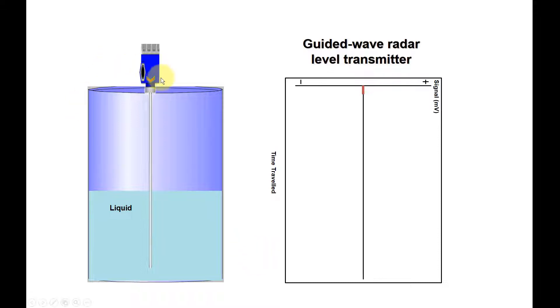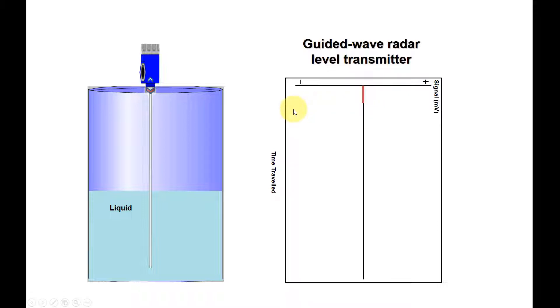First, the radar signal will be generated by the level transmitter electronic board, as you can see here. Then you can see the curve of the signal traveling — the signal will travel and reach this reference point, and you can see the curve is moving this way. Then one of the radar signals will bounce here, because this is a reference line — there is a surface of the tank top. Tank top detected.